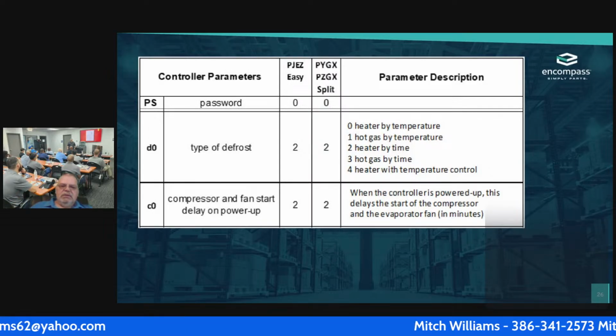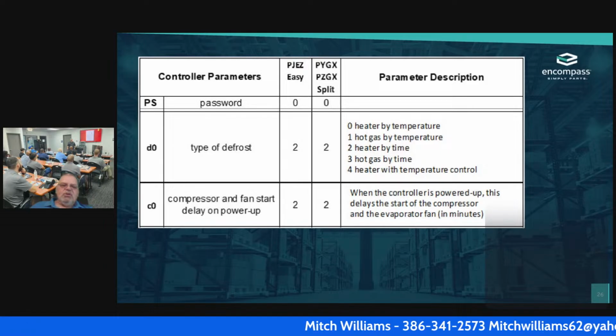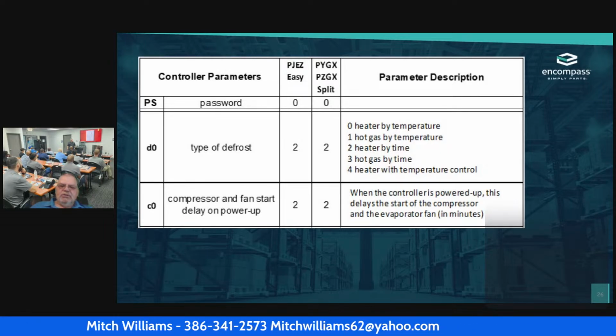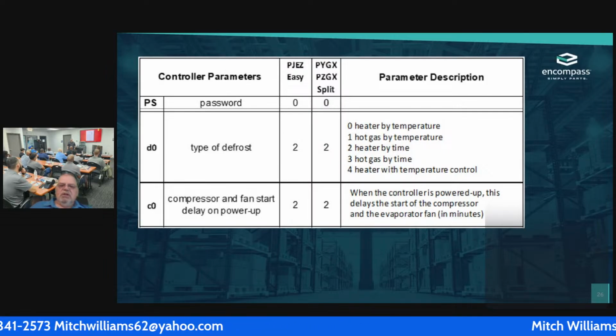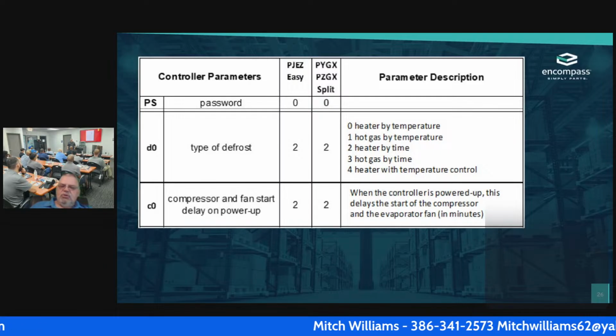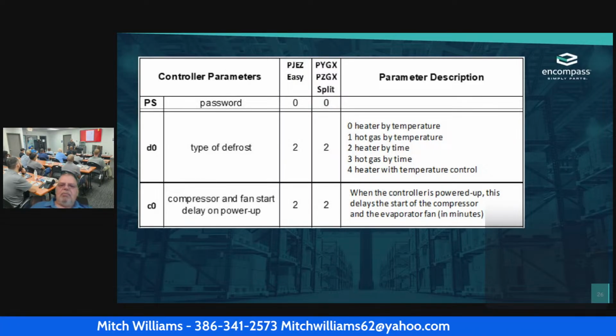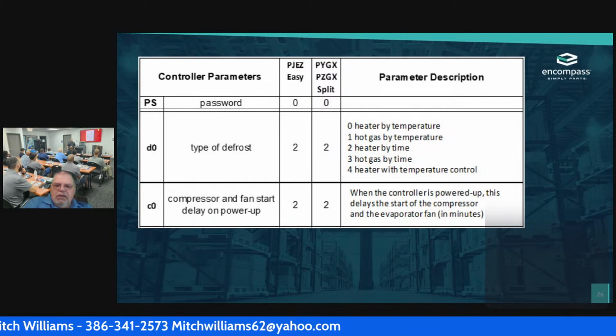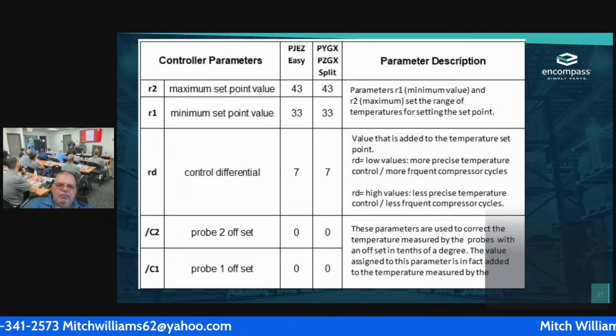Okay, that is the compressor and fan start delay on power up. Both of these are set at 2. So when the control is powered up, this delays the start of the compressor and the evaporator in minutes. So I get 2 minutes. It's set for a 2-minute delay. I can adjust that up. I don't adjust it down. I don't think you can.